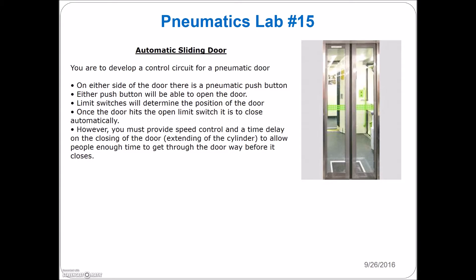You're going to do a control circuit for a pneumatic door. On either side of the door there's a pneumatic push button, so we're going to make use of each of those push buttons — either push button is going to open up the door. Limit switches are going to determine the positioning of our door, and once the door hits the open limit switch it closes automatically.